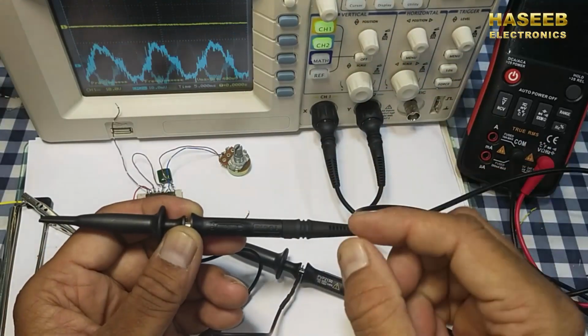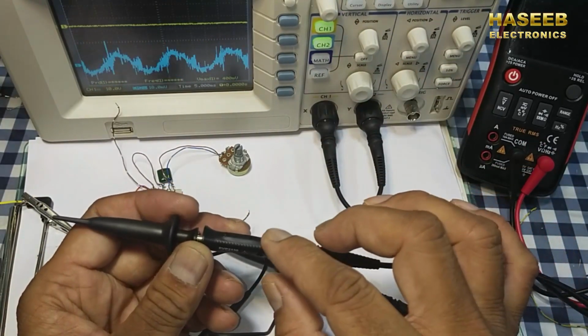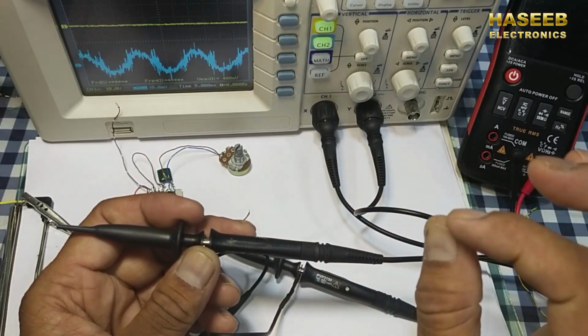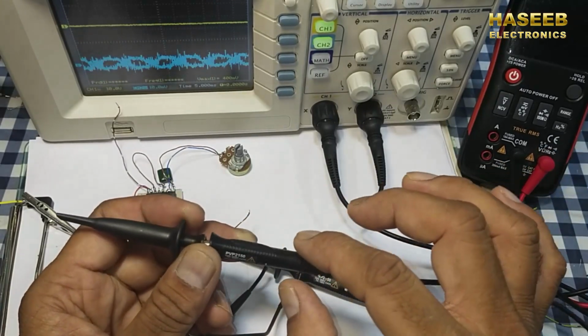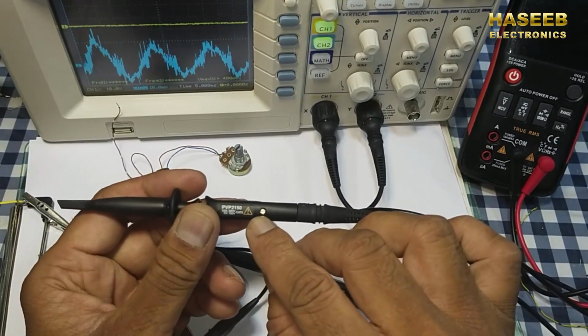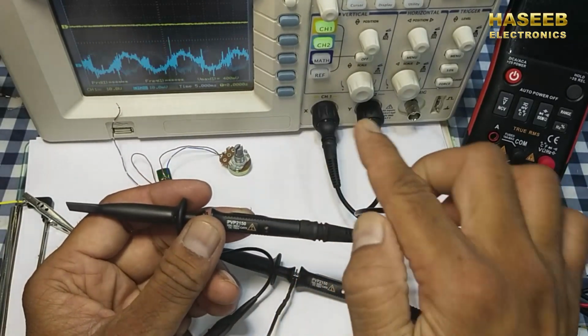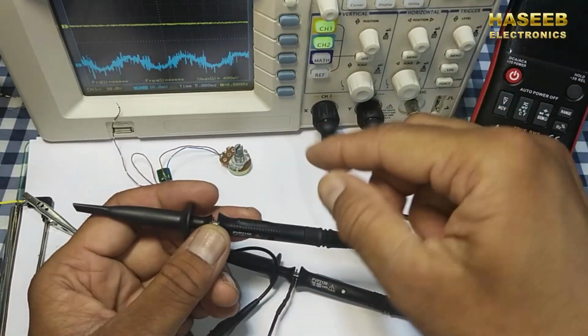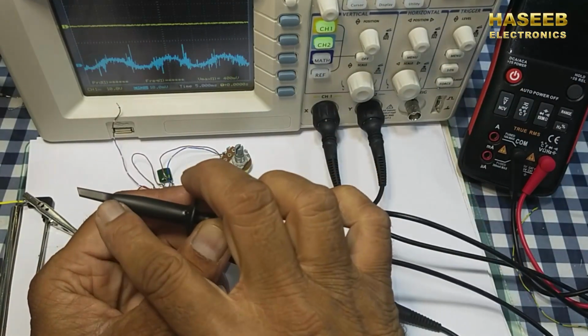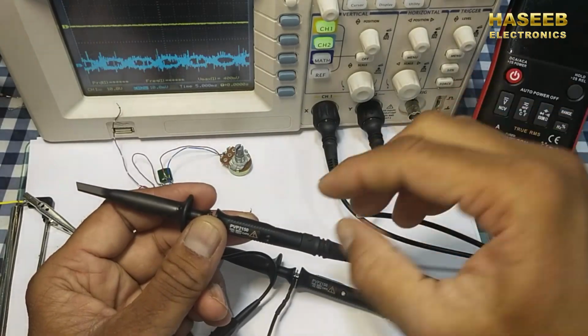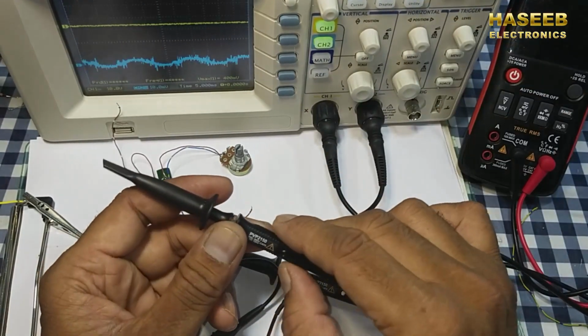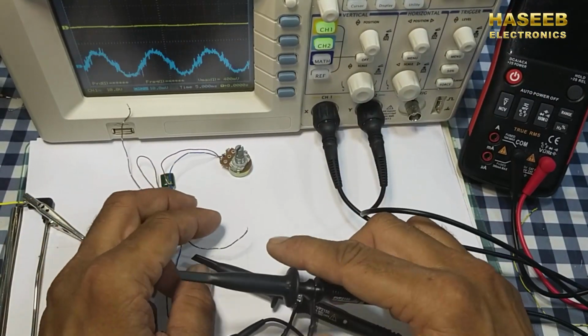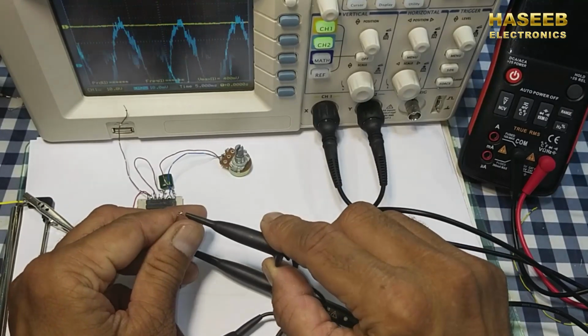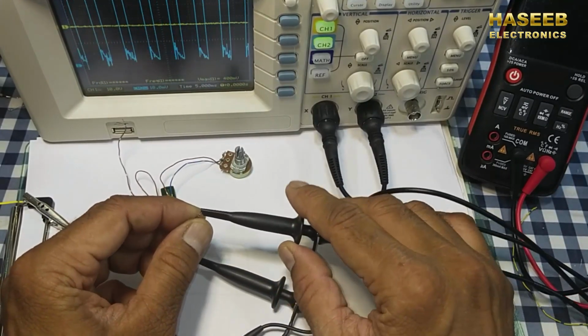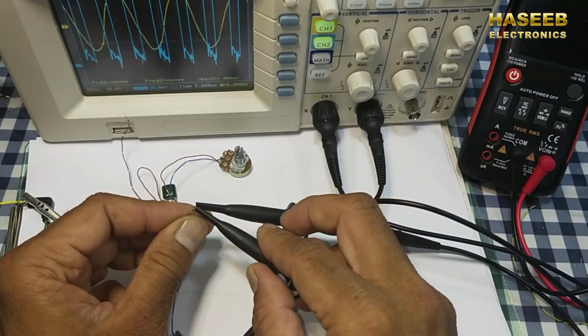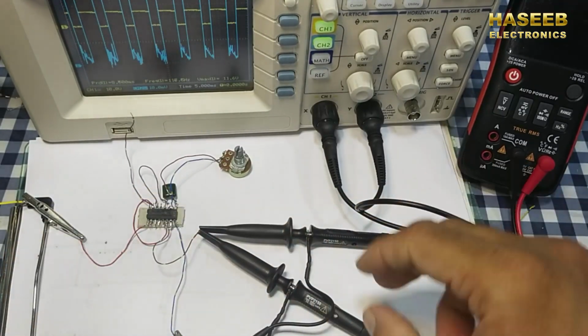When we use a new probe, we have to connect it to a reference signal. We have to calibrate it to read the same reading at 1x and 10x. Okay, I will discuss next time how to calibrate this probe. Now I will connect this probe to this signal, and the same we will connect to the same point.